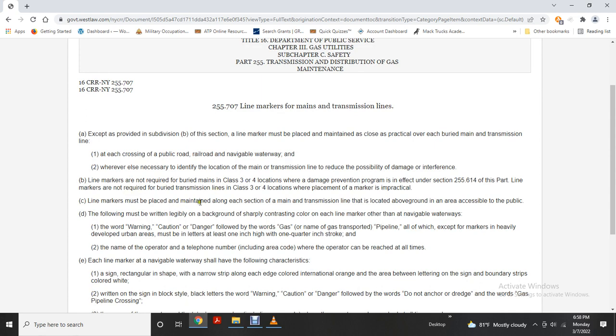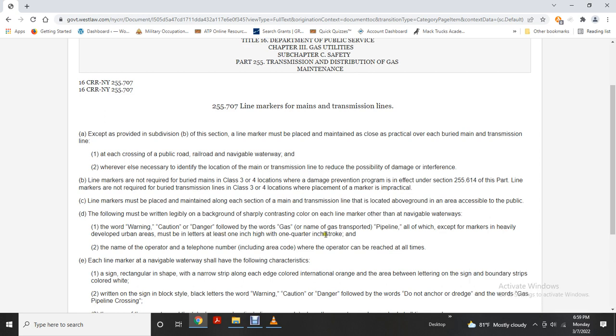Markers and, where practical, line markers must be placed and maintained along each section of the main and transmission line located above ground in an area accessible to the public. The following must be legible on a background of sharply contrasting color: the word warning, caution, or danger, followed by the words gas pipeline, in letters at least 1 inch high with 1/4 inch stroke; the name of the operator; and a telephone number, including area code, where the operator can be reached at all times.